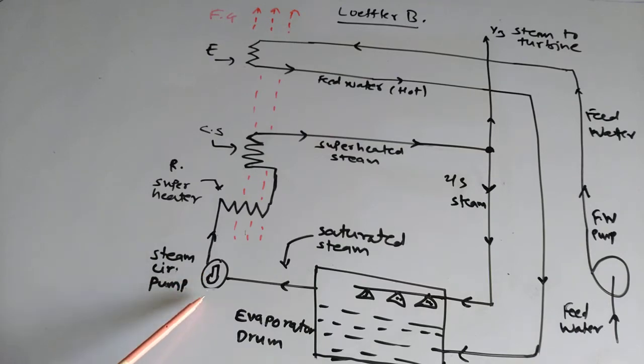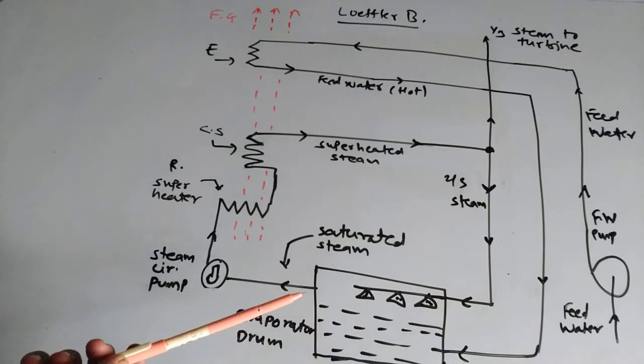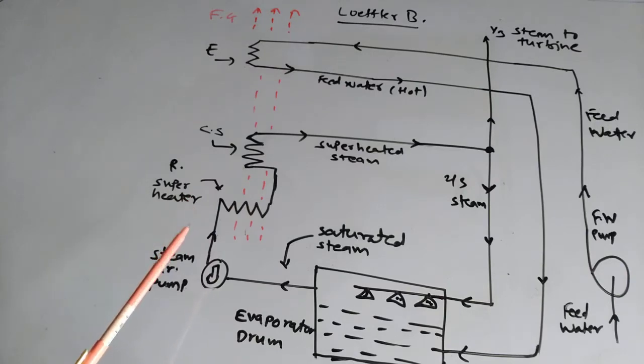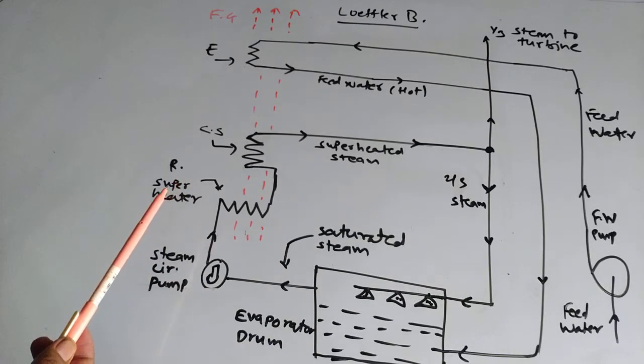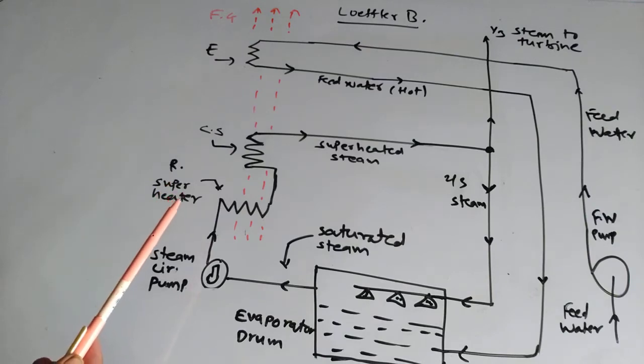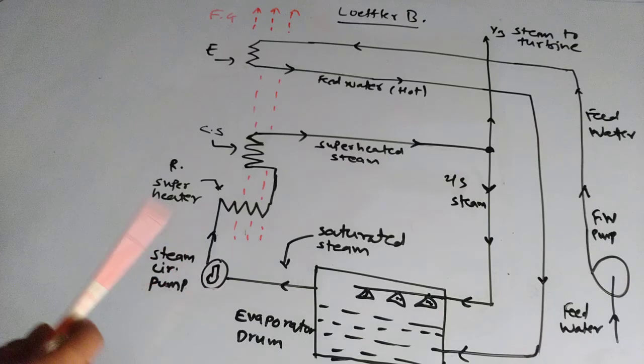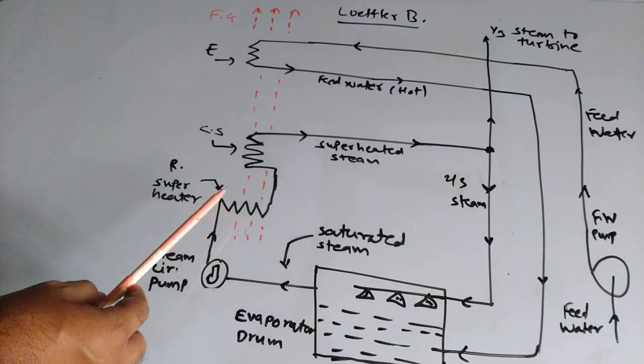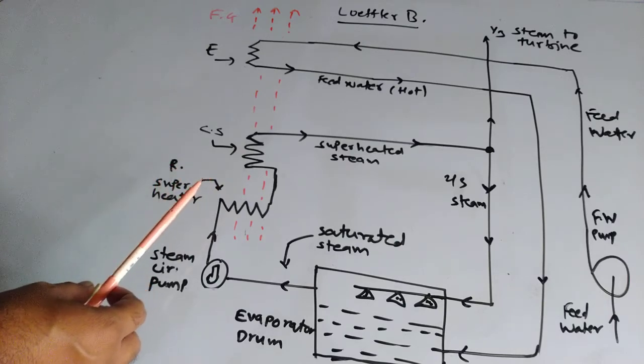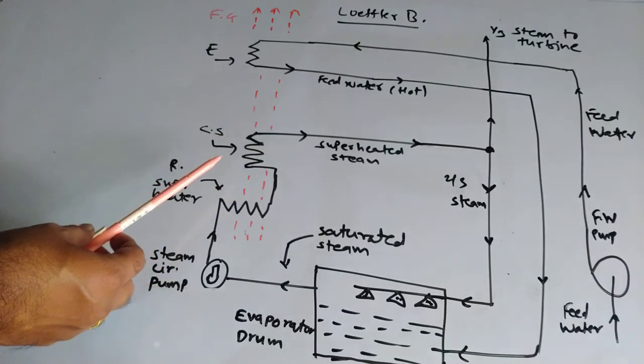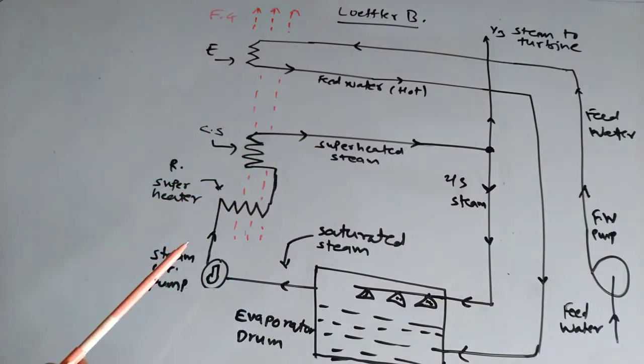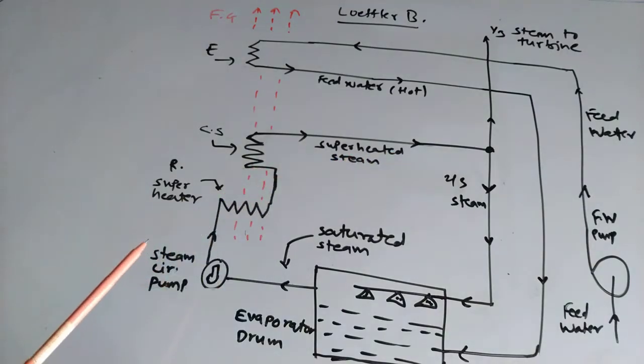With the help of the steam circulating pump, the saturated steam is circulated towards the combustion chamber — specifically towards the radiant superheater. There are two superheaters: the radiant superheater and the convection superheater. Both superheaters receive heat from the combustion chamber and flue gases. In the radiant superheater, the steam is heated by means of flame radiation, and then it is sent to the convection superheater, where it is heated by hot flue gases. The steam then becomes superheated and is sent towards the turbine.